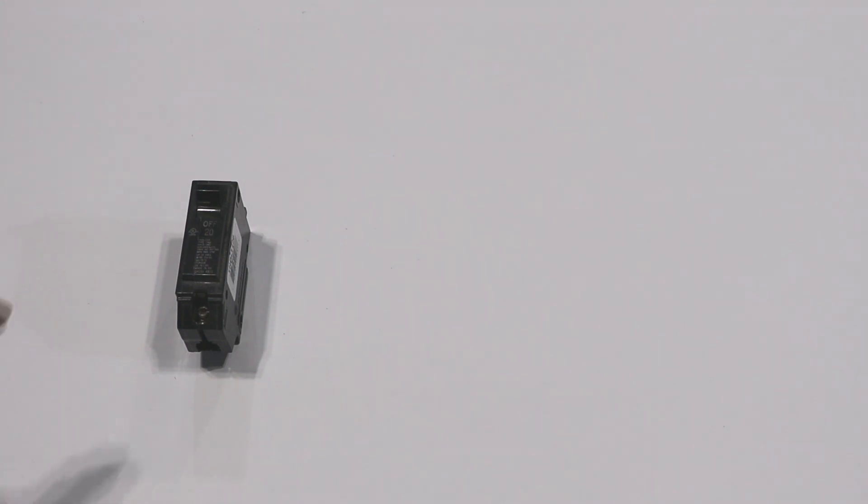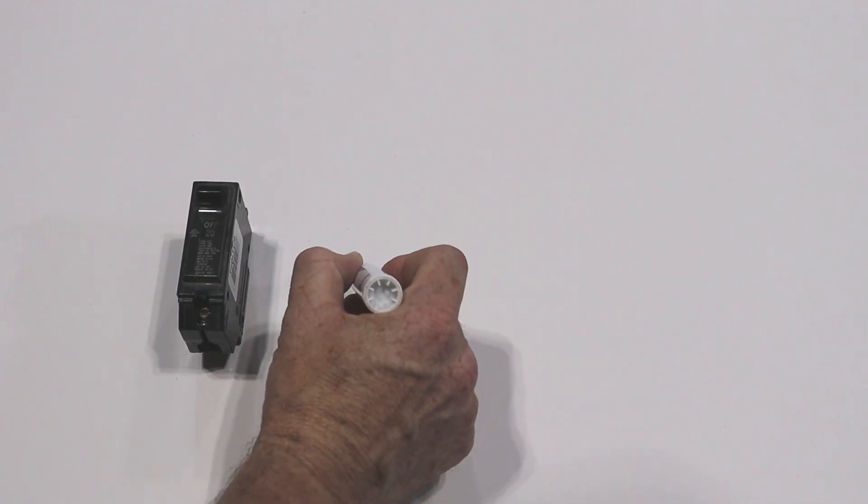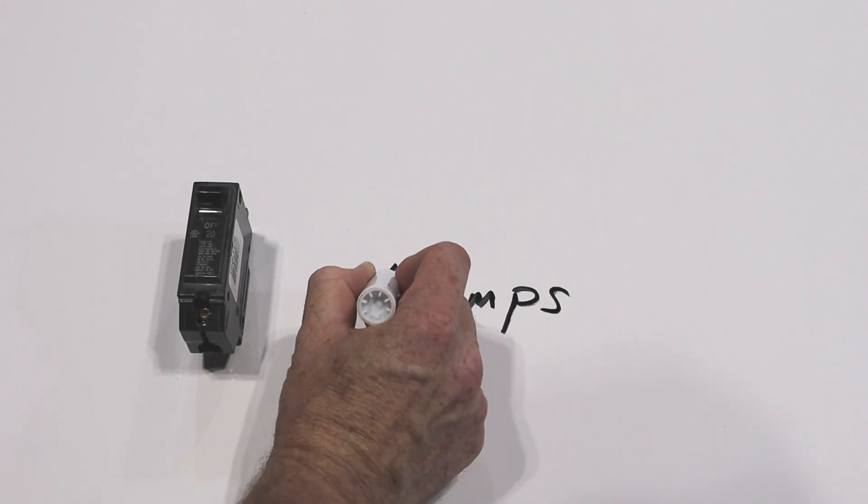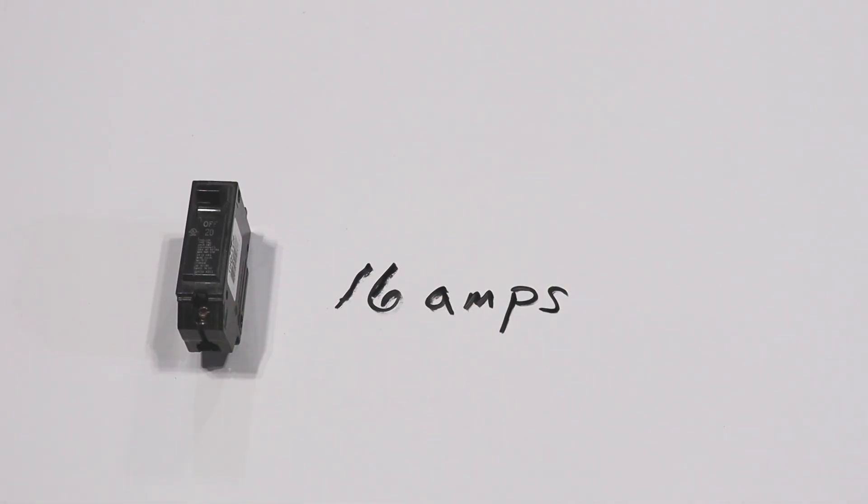Here I have a 20 amp breaker. Breakers are used to power your circuits but they will trip at 80% of the current draw as a safety feature. So if I have a 20 amp breaker I really only have 16 amps to play with on this circuit.